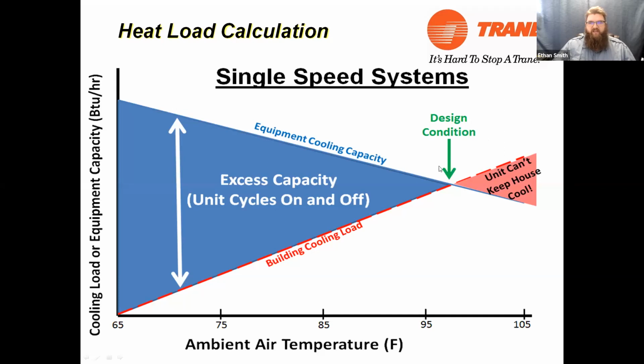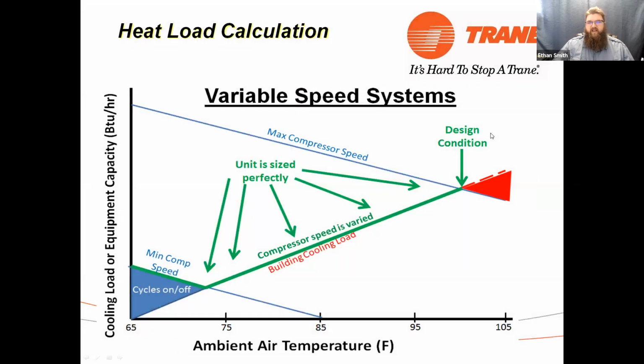The old phrase about zoning is that zoning's really easy until you close a damper. Because once we do that, now we have excess capacity that we have to deal with. So obviously we can stage it, or in the days of variable speed outdoor units, variable or modulating furnaces, variable speed compressors, we can actually break this into hundreds of different design conditions, if you will. So we could have our minimum compressor speed, have our minimum design condition all the way down here around 60, 70 degrees outdoor temperature, and we can match that load all the way up to our maximum design condition if we want. So equipment selection makes a big difference.